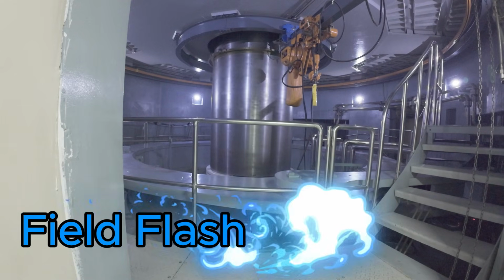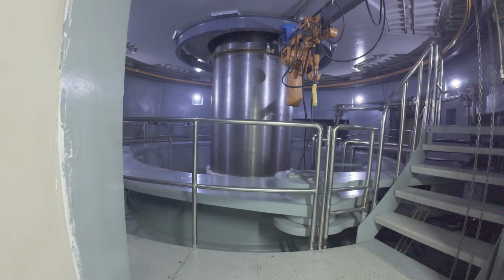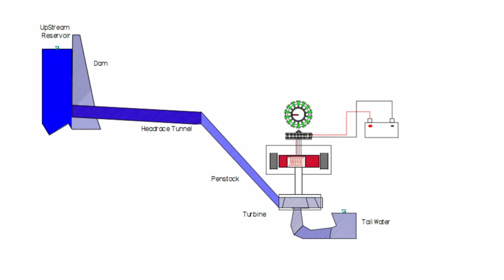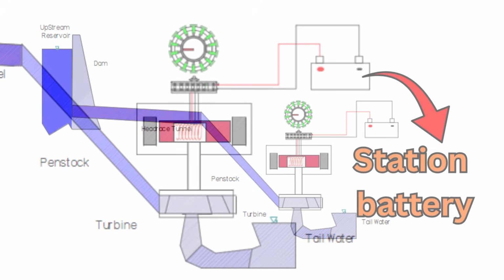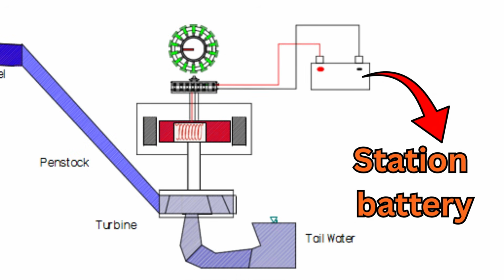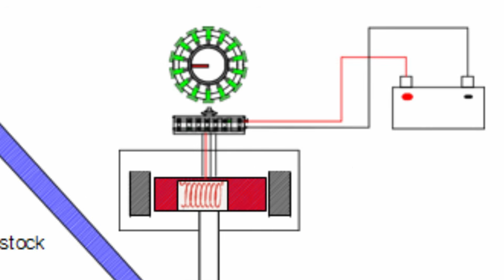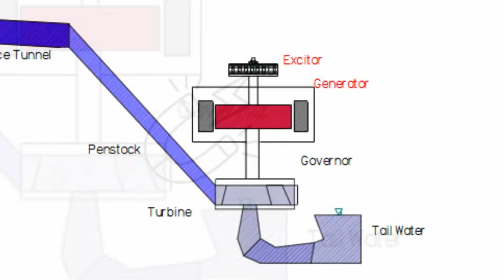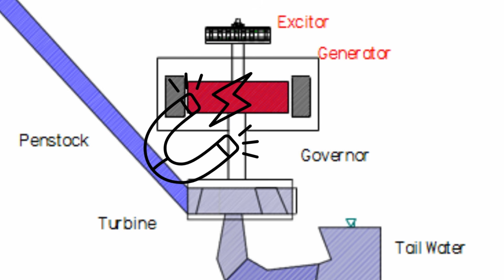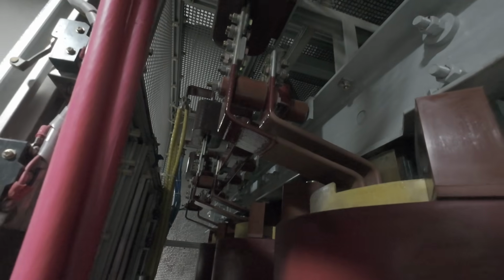It's called field flashing. As the turbine accelerates to near rated speed, the control system temporarily connects the station battery bank directly to the rotor, usually around 110 or 220 volt DC. That current passes through the carbon brushes into the exciter ring and energizes the rotor for the very first time. Suddenly, the stator begins producing a small AC voltage. At first, only a few percent of rated voltage, but it is enough.